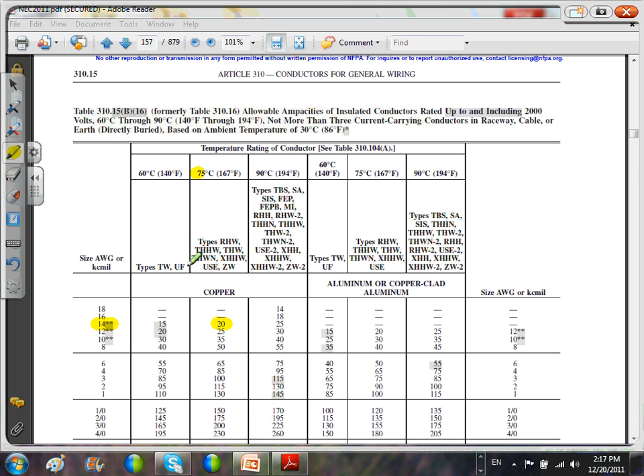Now if you ask me as an engineer, not code-wise, the minimum conductor you should use in any commercial industrial field is number 12. Don't even go to number 14. But code-wise, technically, I can tie 3 conductors, 3-phase, for a 10 horsepower motor that's running continuously. That will be 20 amps. Number 14, 3 of them, good to go. Any questions, any comments, guys?